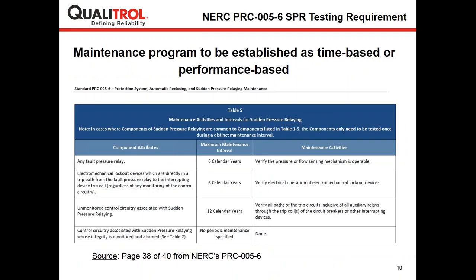Now, the NERC standard establishes the requirements for a maintenance program that needs to be adhered to by utilities and companies that have transformers. The maintenance program can be time-based or performance-based, but for sudden pressure relaying, whether it's an electric unit or a mechanical unit, they must be tested every 6 years. And this can be found on page 38 of 40 of the actual standard.